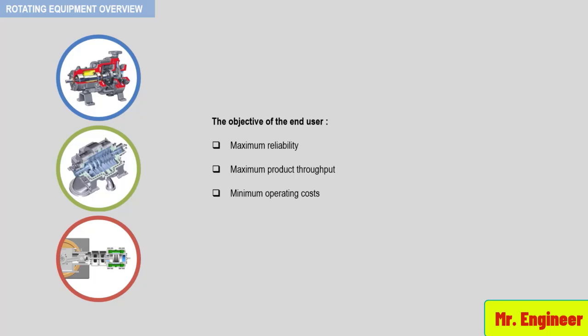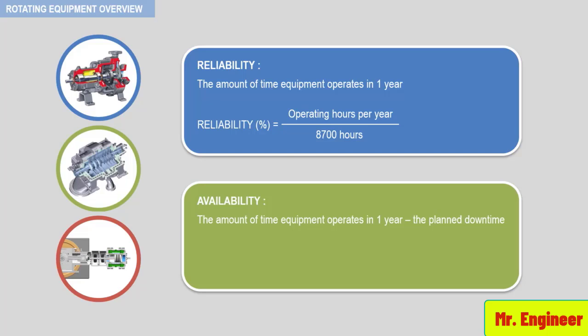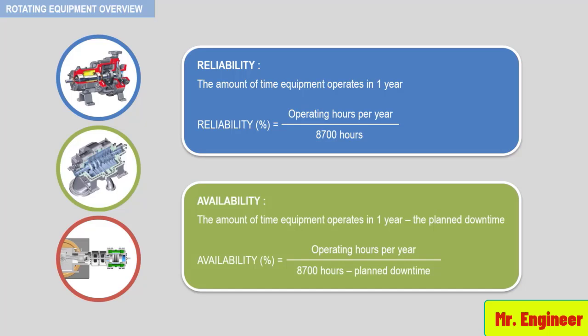The definition of reliability is the amount of time the equipment operates in one year, calculated using the following formula: it is equal to the operating hours per year divided by 8,700 hours, which represents the number of hours in a year. Good reliability and availability indexes are greater than 95%. Reliability does not take into account planned downtime.